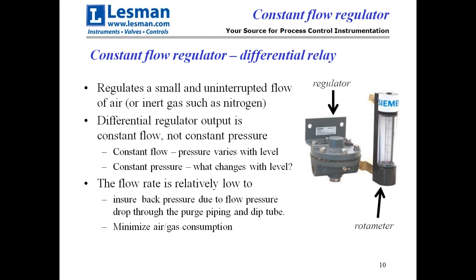When you have constant flow going out, the pressure in the line varies with level because the flow is held constant. This is not like the regulator on your air compressor that maintains constant pressure while flow varies. In our case, we want to measure the pressure, so we create a constant flow. This is done by looking at the differential because, according to Bernoulli's equation, flow varies with the square root of the pressure. If you maintain that, it correlates to the flow going out.